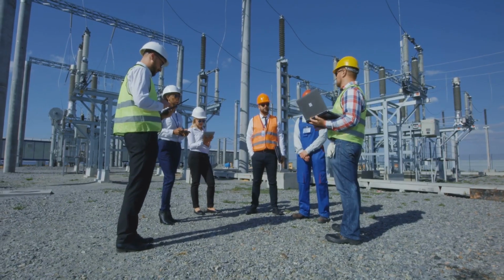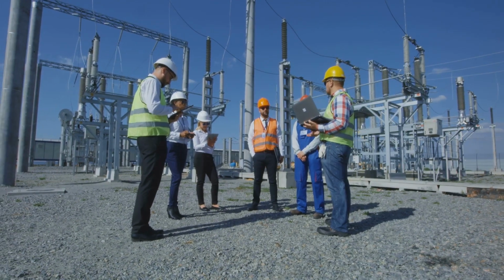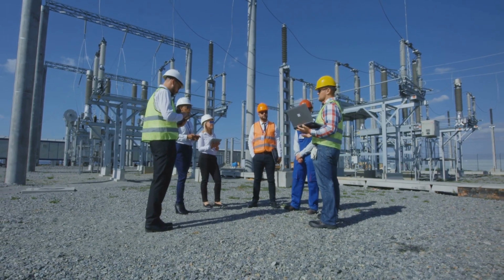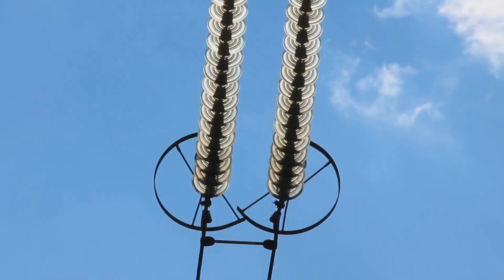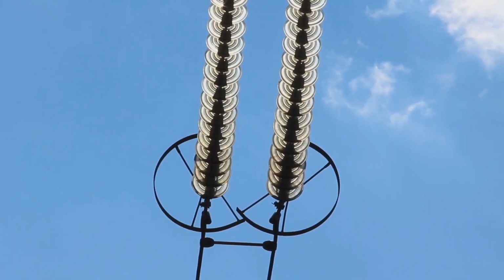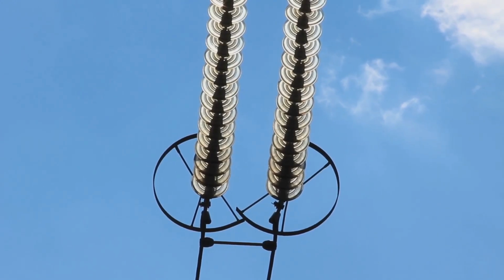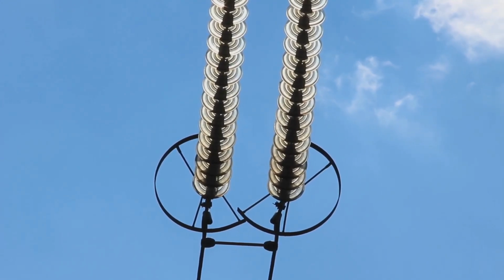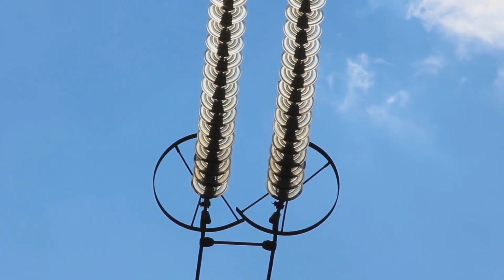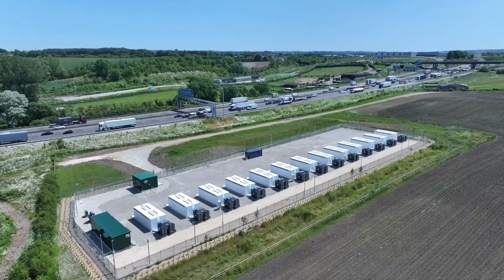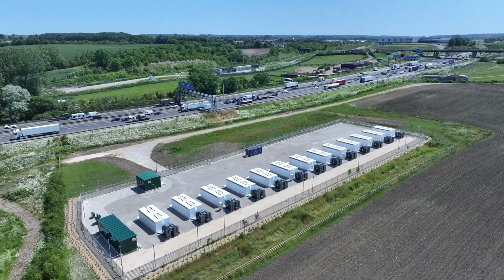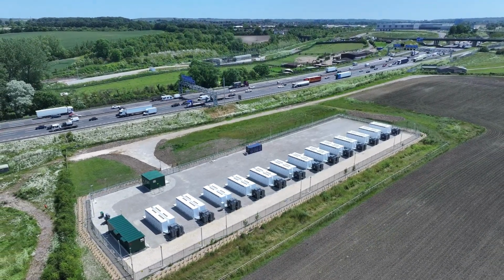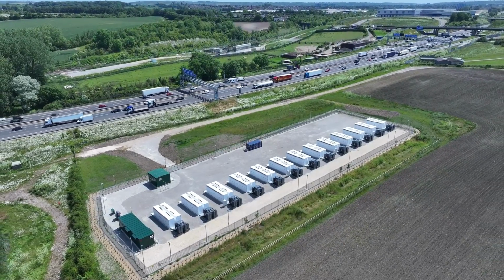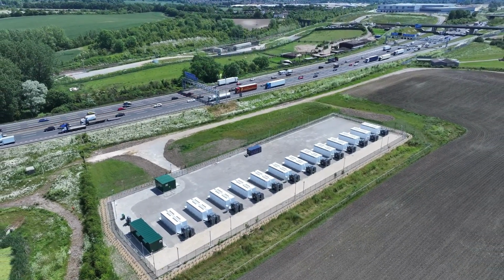In specific cases, like microgrids, campus systems, or critical facilities, intentional islanding is permitted if pre-authorized. But even in these cases, DERs must behave predictably, stabilize frequency and voltage within defined limits, isolate safely, and reconnect only with utility coordination. This matters for FRT because intentional islands may rely on DERs to provide immediate post-fault support, acting like primary generation during system splits.